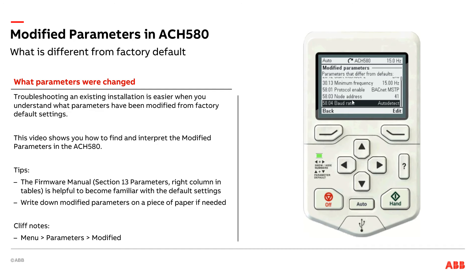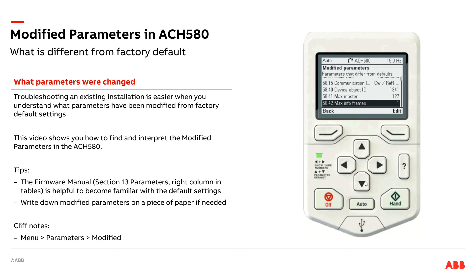Scrolling down, as part of the BACnet configuration there are a couple other settings. My baud rate — I could have programmed the dedicated baud rate, but when you enable BACnet, it's going to try to auto-detect the baud rate for you. I have com loss configured for BACnet. I can see my device object instance ID; I went with 1341 — so maybe this is the 13th building on campus and the 41st device in there, or region 13 on the fourth floor and device number one. There are a lot of creative ways to set up a device object instance ID numbering system. I've also got max master, which got configured because of BACnet — a couple more settings that were all a result of turning BACnet on.